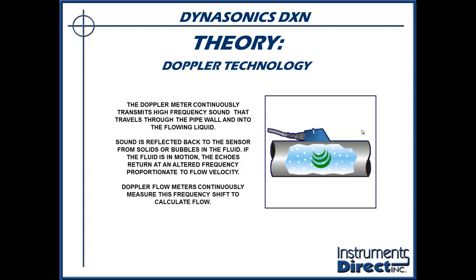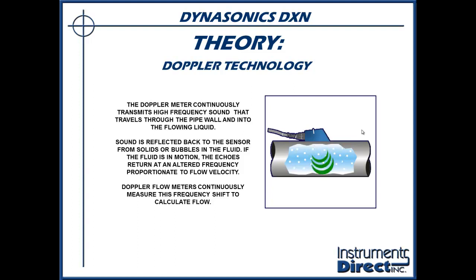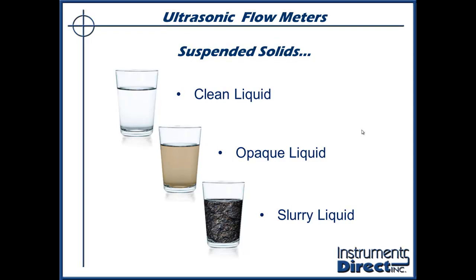A key item with the Doppler flow meter is it needs suspended particulate matter in the process stream — or you get nothing. The analogy is a police radar gun: it transmits a frequency, bounces off a car, comes back, and says the car is doing 100 miles per hour. No car on the road? No signal back. Ultrasonic Doppler flow meter with no solids in the pipe? No signal back. The house rule is 100 parts per million, 30 microns or larger, of suspended solids or aeration for this to work. For reference, the tip of a pencil is about 100 microns.